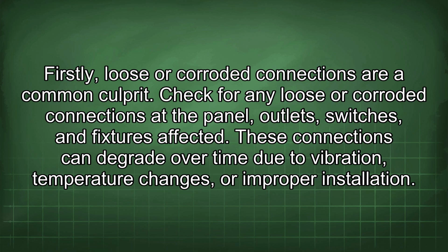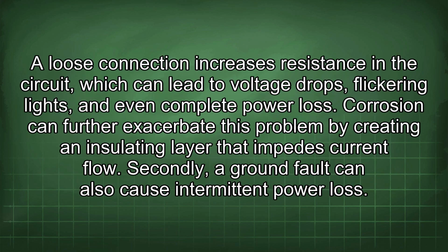Firstly, loose or corroded connections are a common culprit. Check for any loose or corroded connections at the panel, outlets, switches, and fixtures affected. These connections can degrade over time due to vibration, temperature changes, or improper installation. A loose connection increases resistance in the circuit, which can lead to voltage drops, flickering lights, and even complete power loss. Corrosion can further exacerbate this problem by creating an insulating layer that impedes current flow.